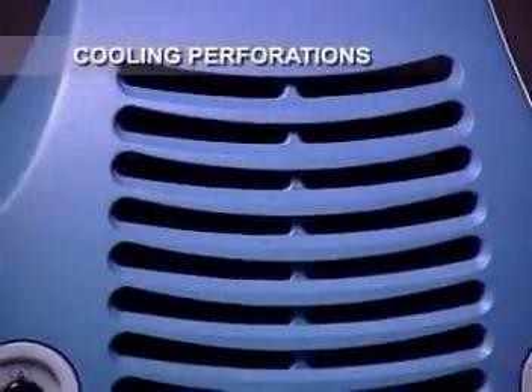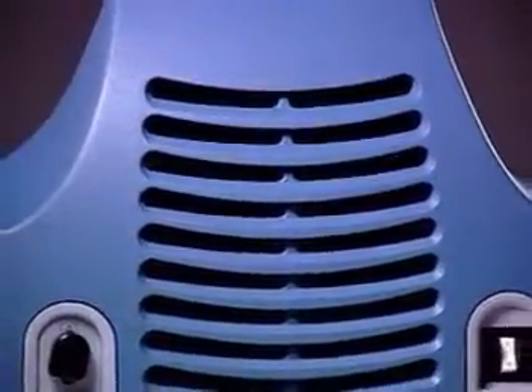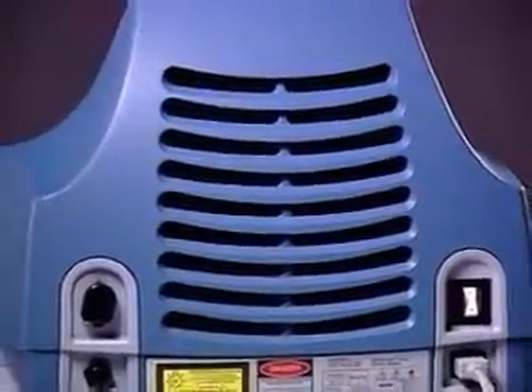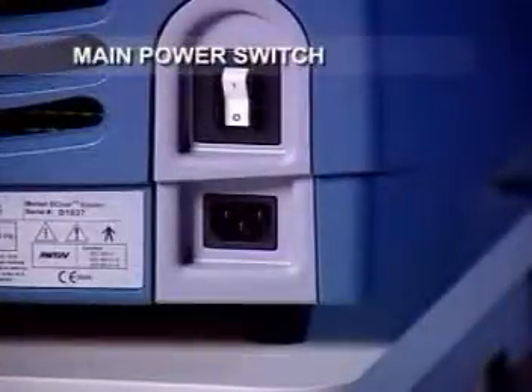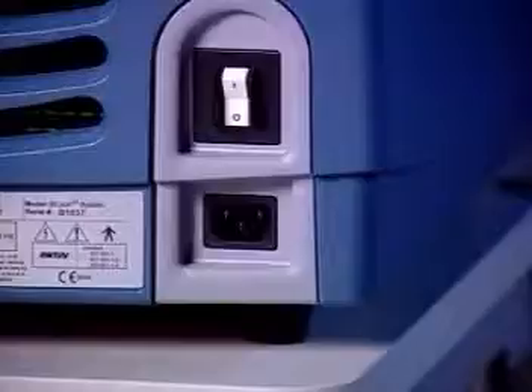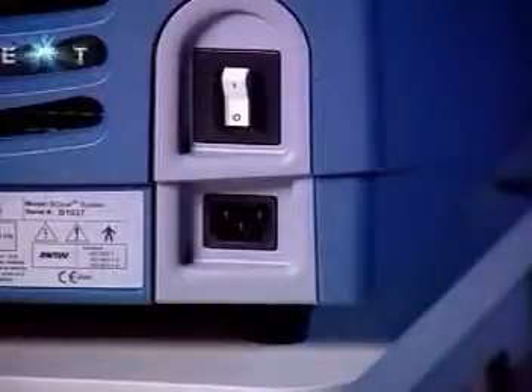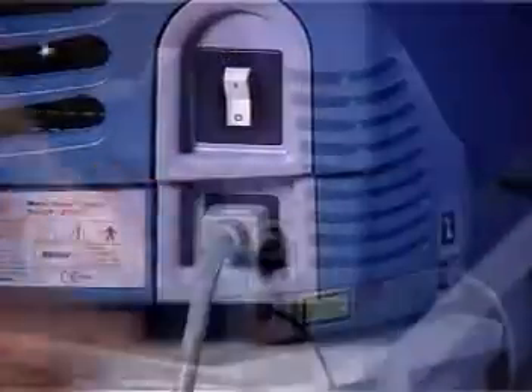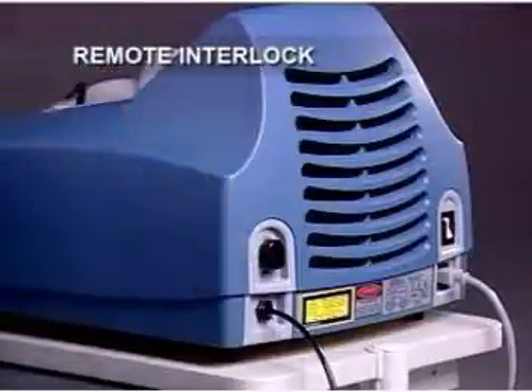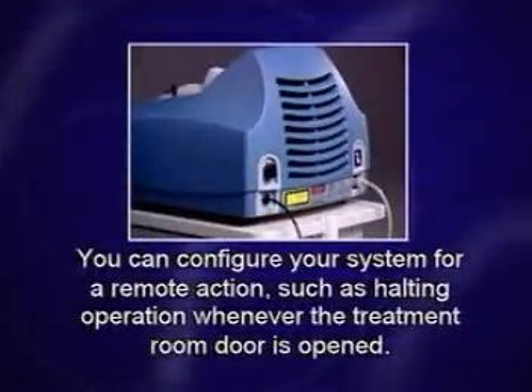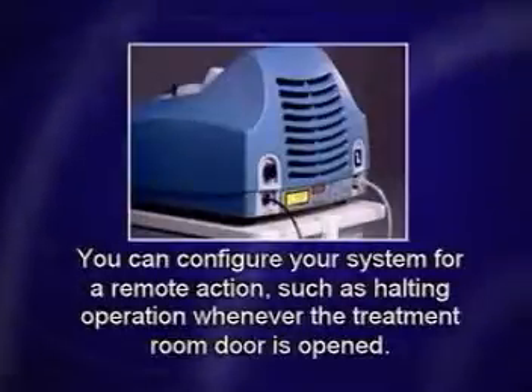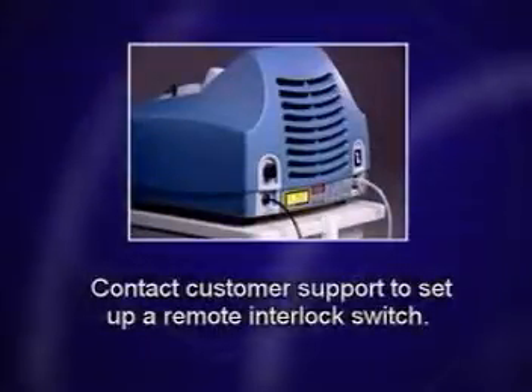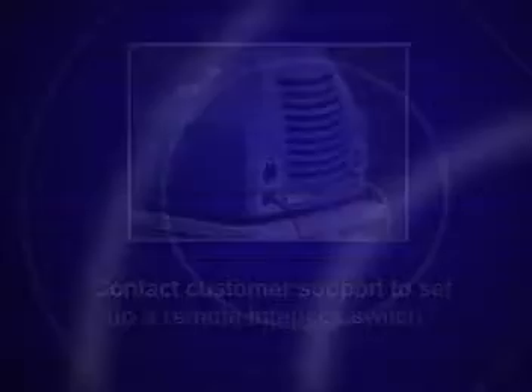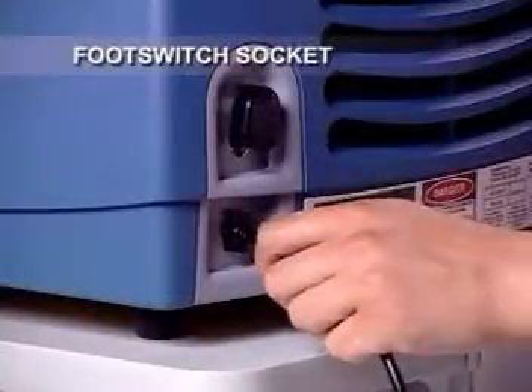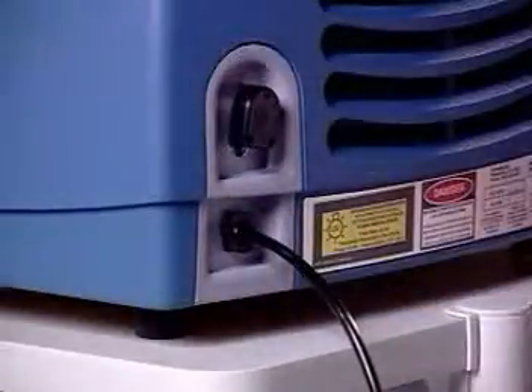Cooling perforations. Be careful never to block or cover the cooling perforations when the system is running, as overheating can occur. Main power switch. The main power switch acts as both a circuit breaker to protect against excessive current and a switch to turn the unit on and off. Power cord socket. Remote interlock converter socket. You can configure your system for a remote action, such as halting operation whenever the treatment room door is opened. Contact customer support to set up a remote interlock switch. Foot switch socket. The foot switch socket accepts the pneumatic tube from the foot switch.